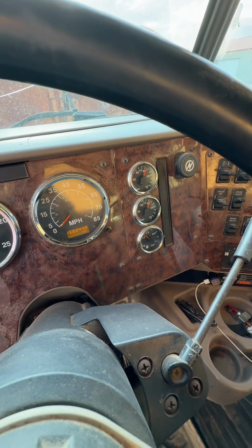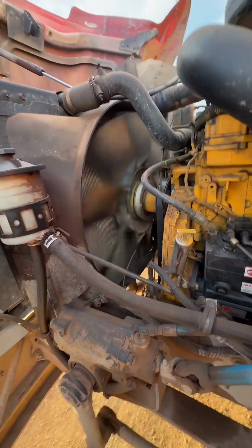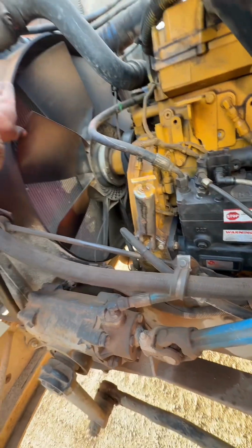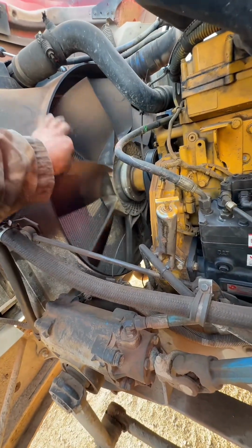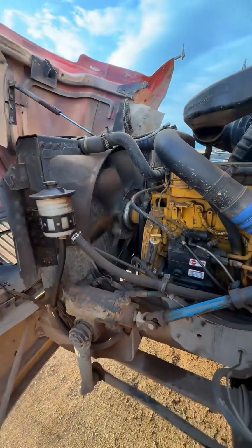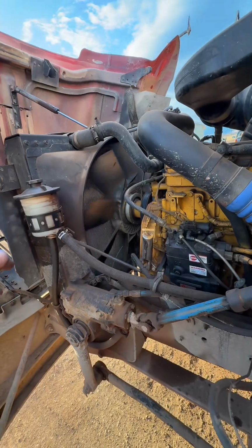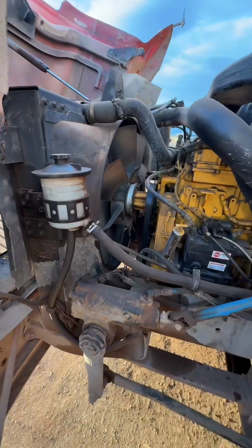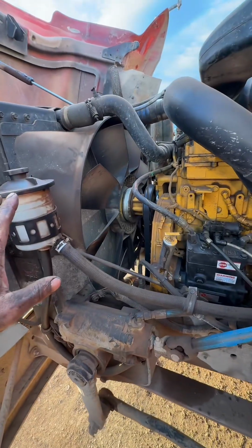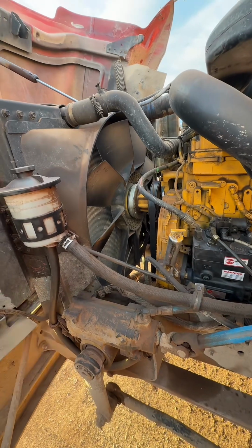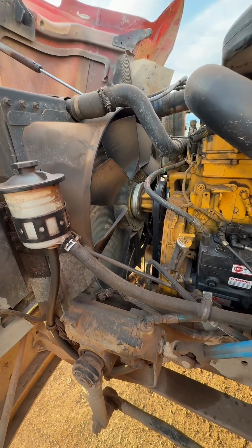All right, now that we have enough air pressure, the fan has completely shut off. So basically, the issue that we're having is going to be AC related. So he said that it would turn on and turn off at random times, and that is controlled by the high pressure on the AC compressor itself. So when the fan is acting crazy, where it turns on, shuts off, turns on, shuts off, which is what he was explaining to me.